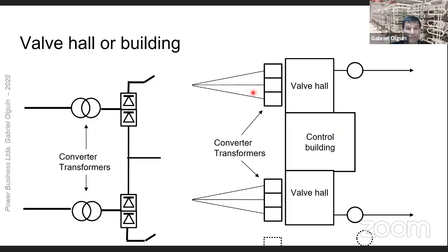Valve hall or valve building. The valve hall is the building which contains the thyristor valves. One of the main functions of the valve hall is to minimize pollution within the hall. Cooling air is required since thyristors and electrical equipment generate heat. The air inside the hall is maintained at positive pressure with respect to atmospheric pressure so that pollution is kept outside the building. This example shows 3 converter transformers per pole side by side with the valve hall.